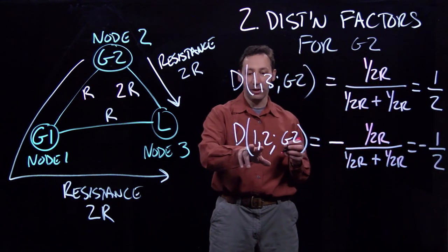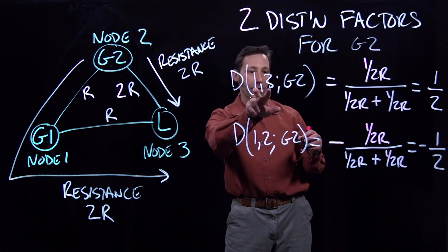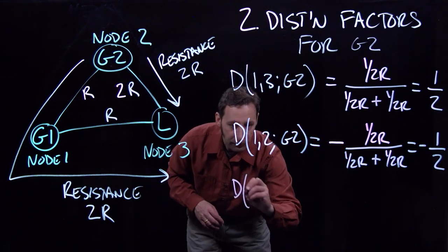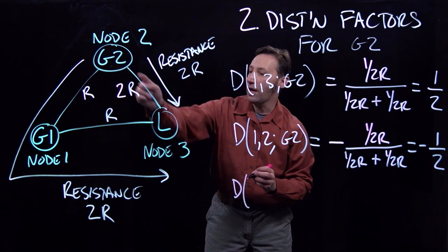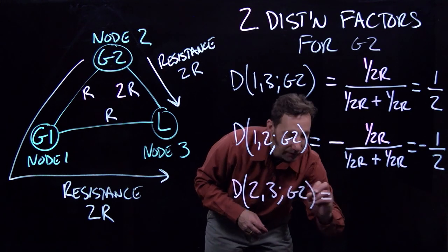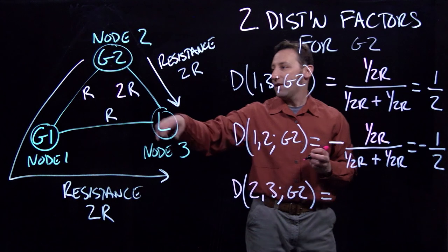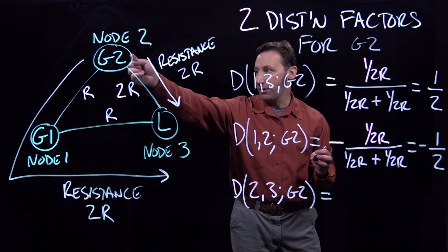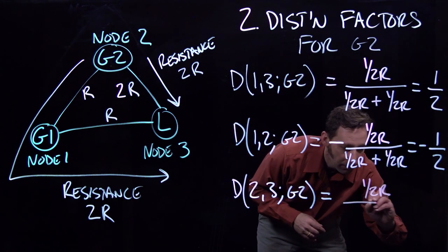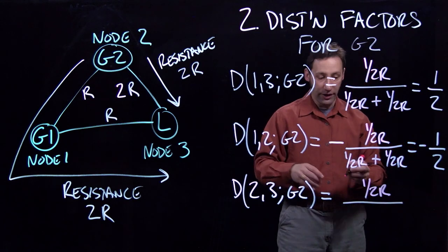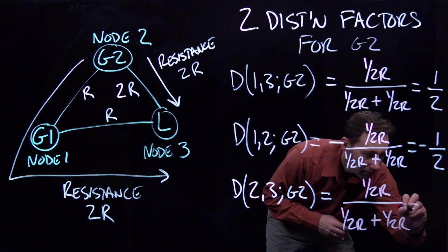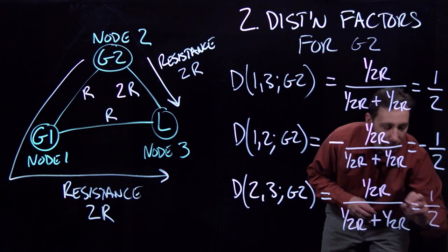The distribution factor on line 1 to 2 has the same magnitude as line 1 to 3, just with a negative sign. Finally, we calculate the distribution factor on line 2 to 3 from G2. In the numerator, we have the inverse of the resistance of the direct path from 2 to 3, which is 1 over 2R. The denominator is the same as in the other distribution factors, and again we get one half.